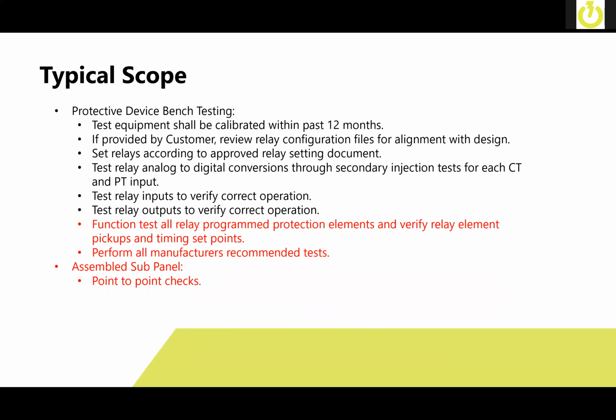From an assembled sub panel before we go out in the field, we recommend that you have that panel manufacturer perform point-to-point checks to minimize troubleshooting or miswiring in the field that could cause other issues.